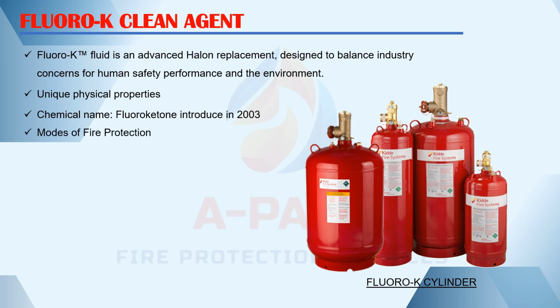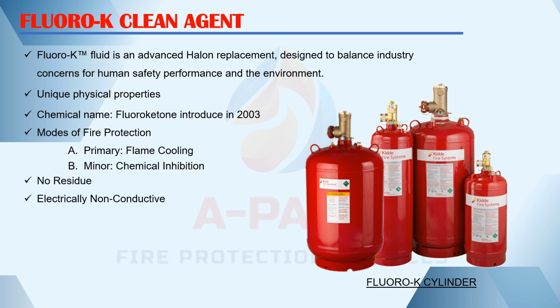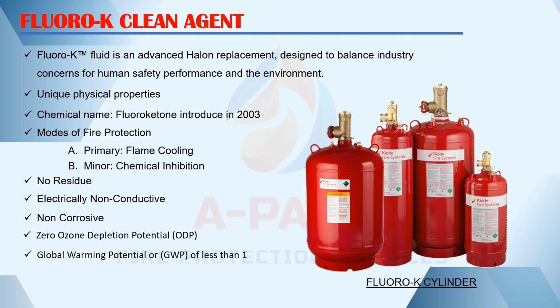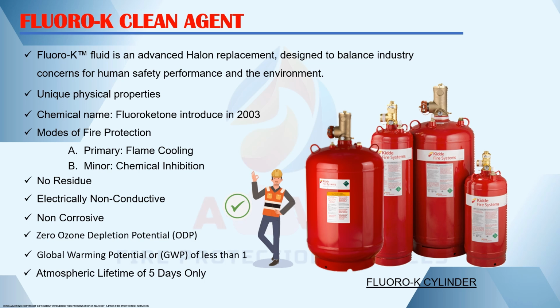Modes of fire protection: A, primary, flame cooling, and B, minor, chemical inhibition. With no residue, electrically non-conductive, and non-corrosive. Zero ozone depletion potential or ODP, global warming potential or GWP of less than 1, and an atmospheric lifetime of only 5 days.